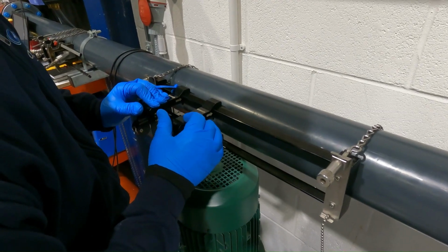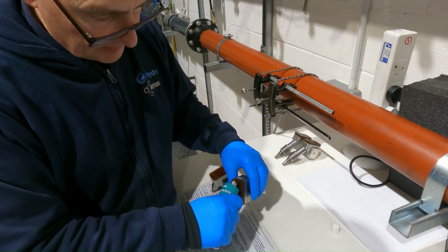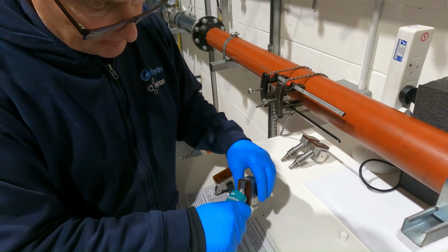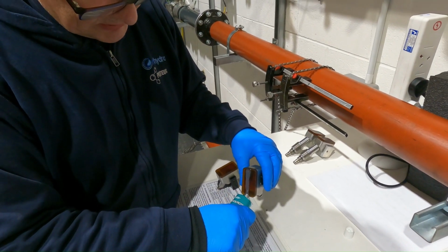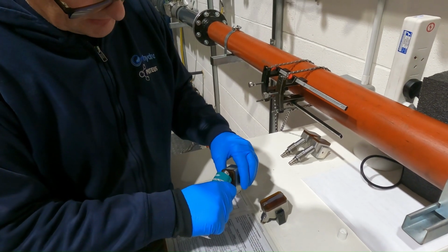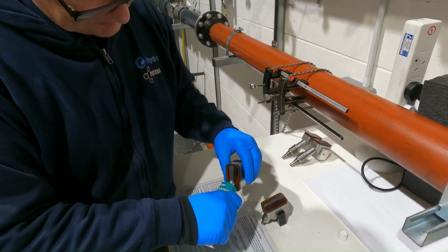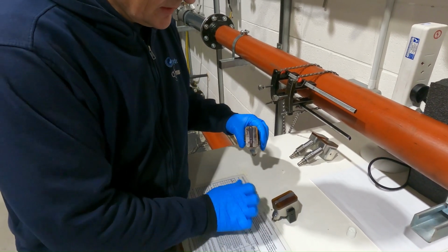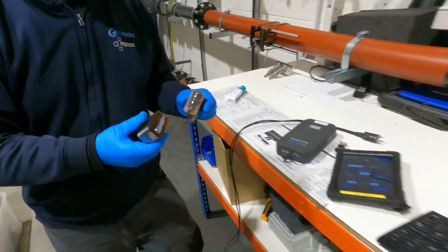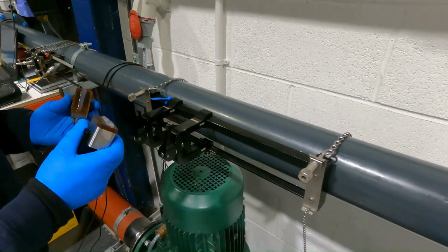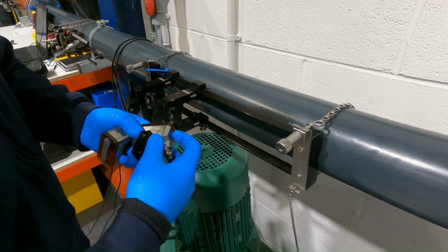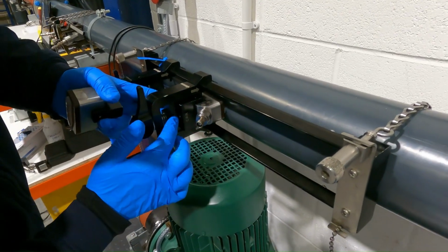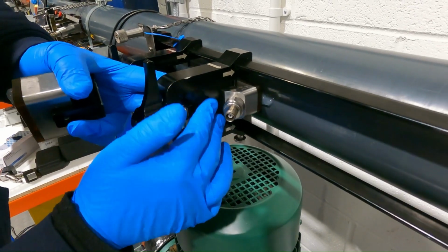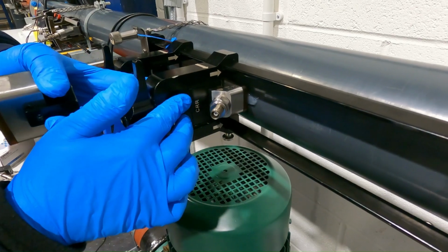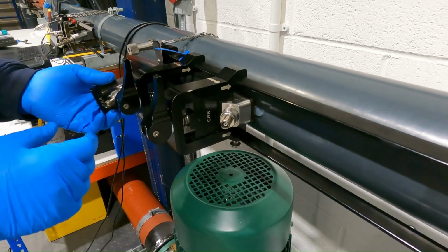Make sure the clamps are primed. Now we need to apply the couplant. So don't go mad, just a nice stripe down the middle, just like putting it on a toothbrush. Okay. And now we go over to the clamp. That just slides in there. There's a little ball bearing there, and that'll click in. Just make sure that it feels flush there, then you know it's set. Same with the other one.